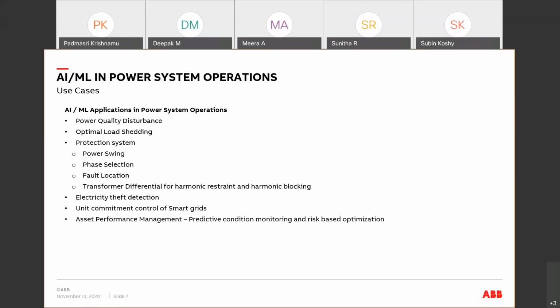Distance protection is a very widely used protection scheme, because there are a lot of high voltage transmission lines, and this protection scheme is used extensively. But this protection principle possesses peculiar advantages, but also has some serious shortcomings. When you're talking about distance protection, we are always looking at the locus of the impedance. Power swing, which is not actually a fault condition, will also have an impedance locus which will not allow the distance protection to operate correctly.